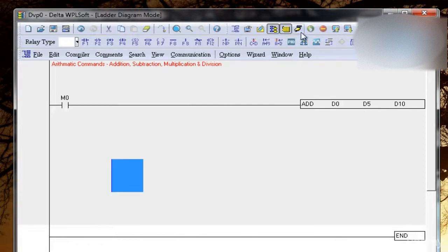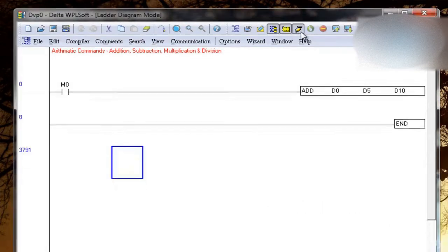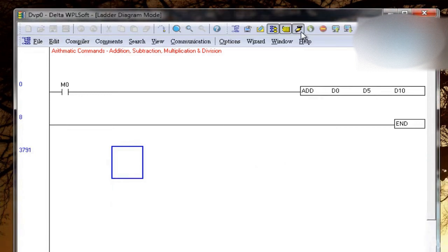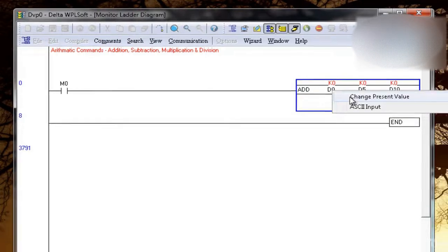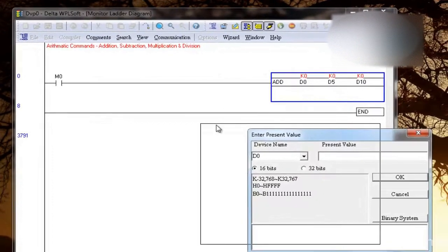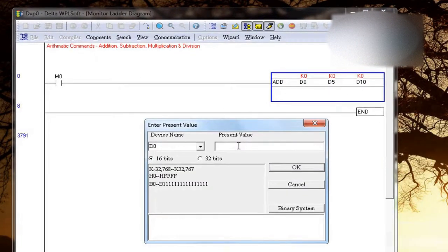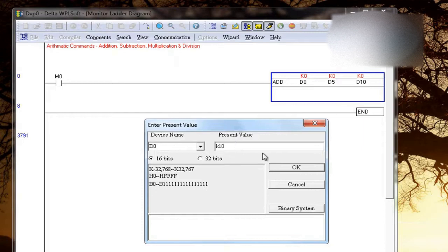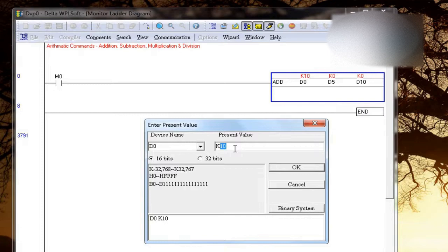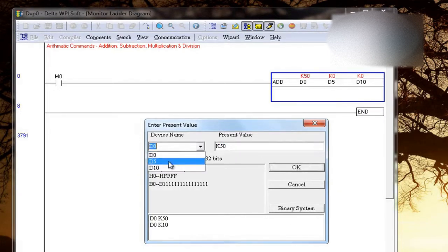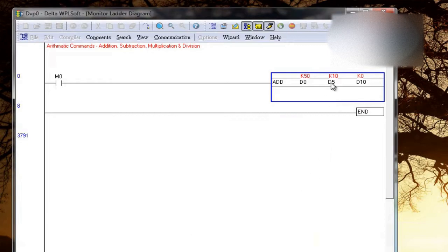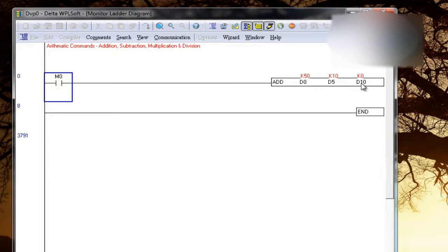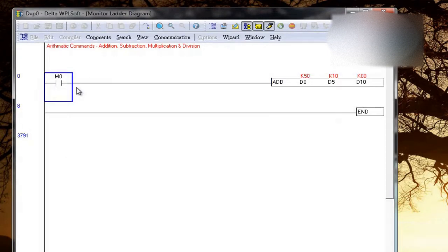So this is the instruction, let me download. Now initially D0 and D5 are 0, so let's change the value. I'll right-click, change present value and D0 I will take K10, you have to write K. So this got 10 and D5 I will write K50. Oh sorry, this is D0 and D5. I have 50 here and 10 in D5. So if I execute M0, it will add these two and store the result in D10. So 50 plus 10 is 60, so you have 60 in D10.